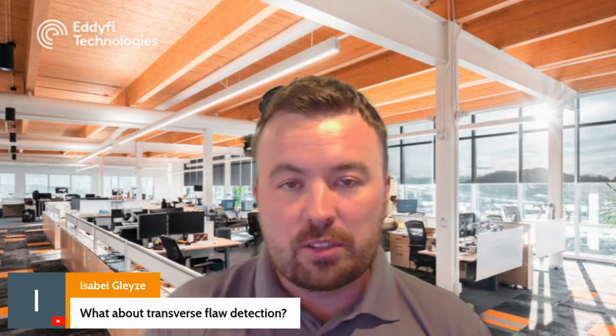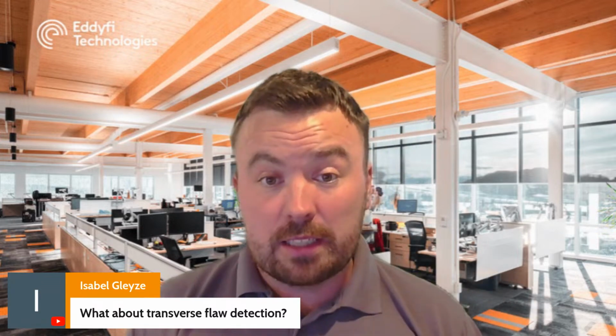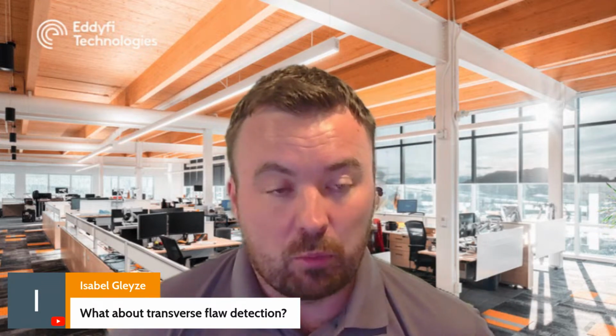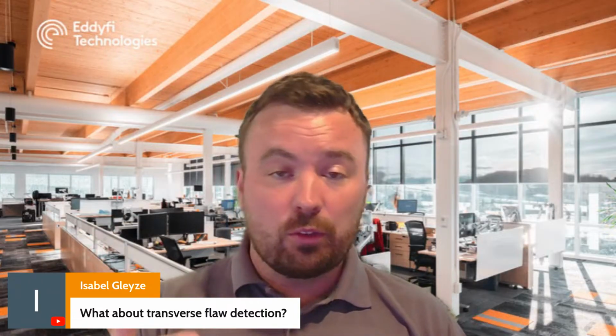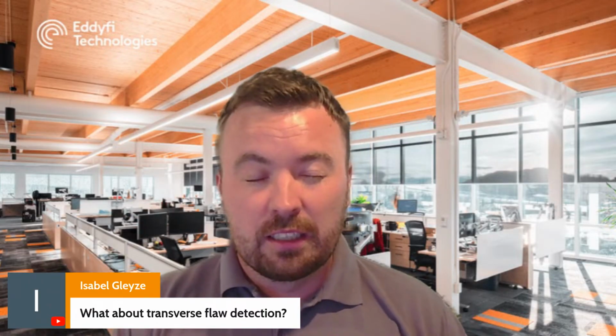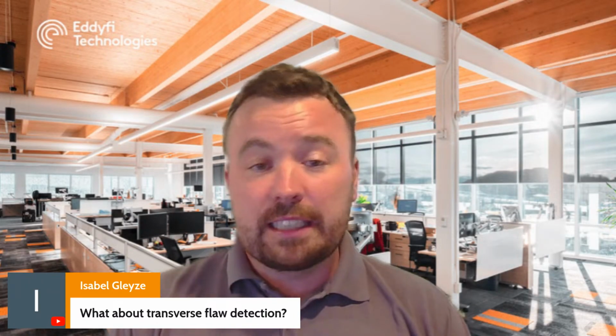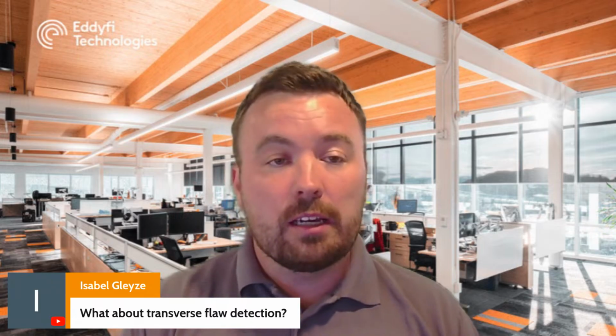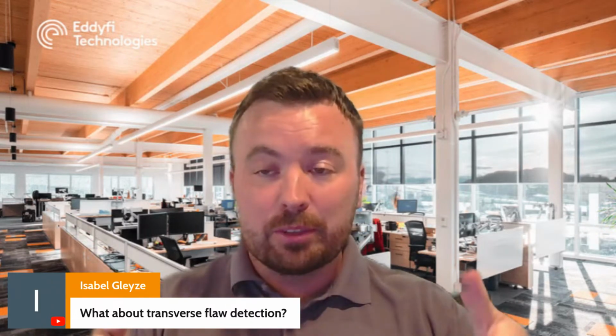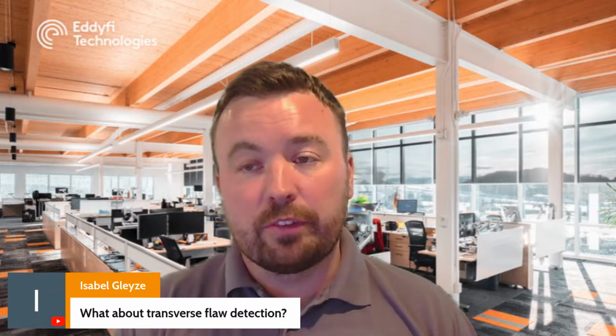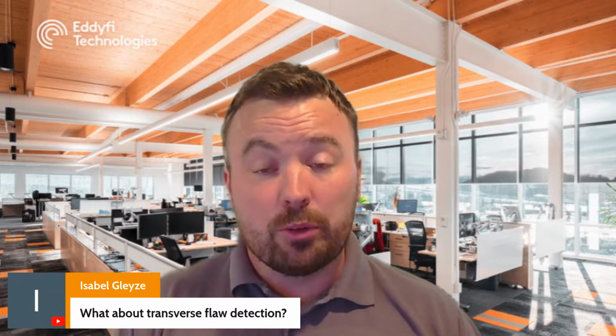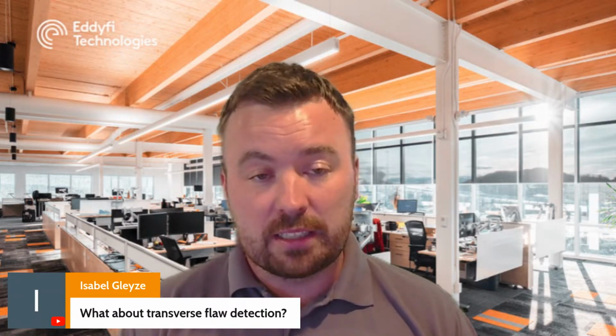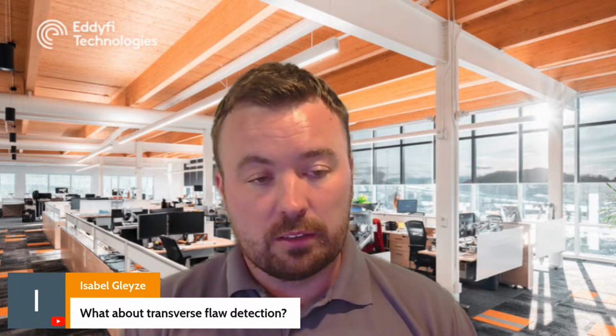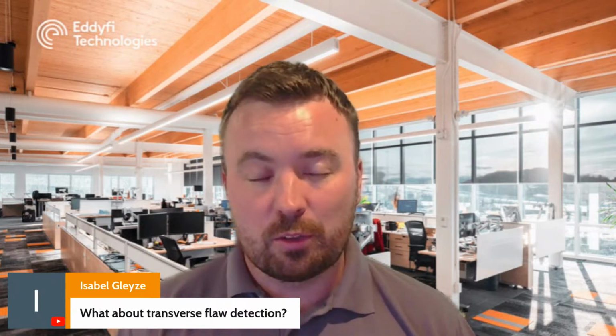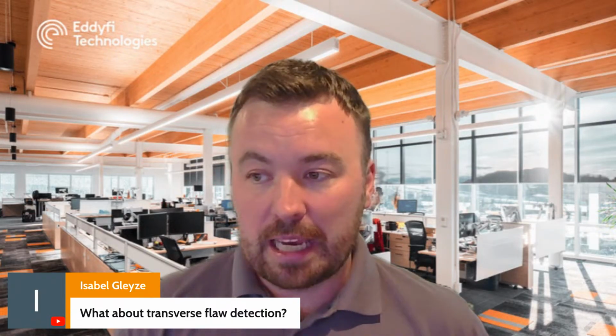First question, what about transverse flaw detection? Yes, in lots of cases for these pipeline welds, we need to be able to detect transverse flaws, those that are 90 degrees to the weld direction. In this case, we use dedicated channels, typically using conventional probes with beams skewed in a pitch catch configuration, looking at the ID and OD. So we have setups for that, which we add to the scanner. And of course, there's a capability there to handle that in the software and the instrumentation. So they can be added.